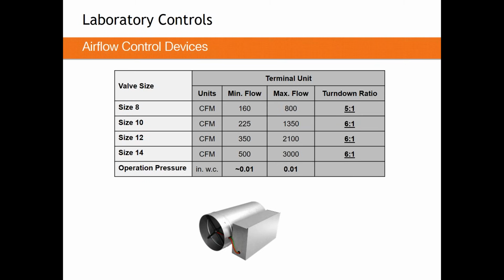So we have to read these charts in a certain specific way. I'll always refer to the size 8 box here just to keep it comparing apples to apples. On a size 8 VAV box, you can get about 800 CFM through it. The minimum would be about 160, giving you a turn down of 5:1. To get 800 CFM out of a size 8 box, you need 0.01 inches of pressure to push that air through the device. Now you have to remember how a manufacturer tests these devices. We get to open the damper wide open and take as much pressure out of the system as we can, and then test what this looks like. So that 0.01 is a minimum.